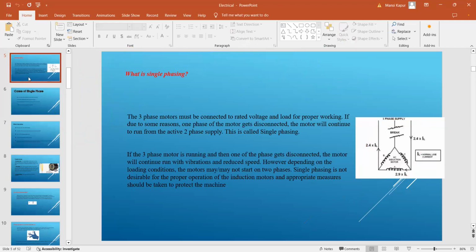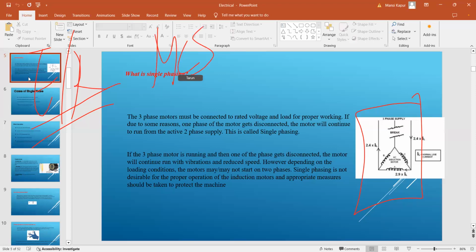Okay. If the three phase motor is running and then one of the phases gets disconnected, the motor will continue to run. Suppose you are taking the engine room round, how will you get to know this motor is single phase? Suppose this is your seawater pump motor, main cooling seawater. How will you get to know in the round that this motor is single phased? Sir, it will take more current and the motor will heat up.